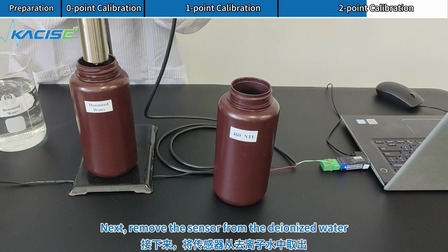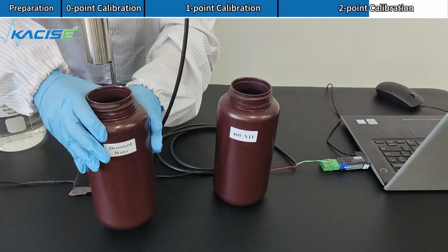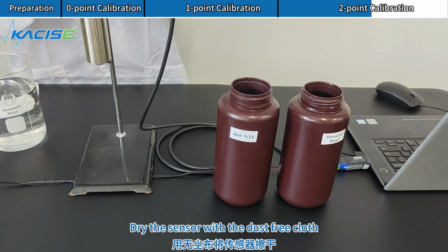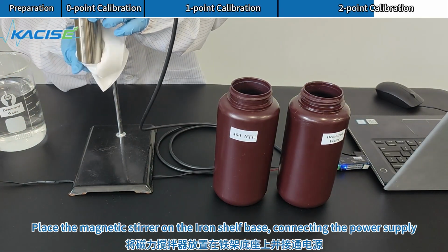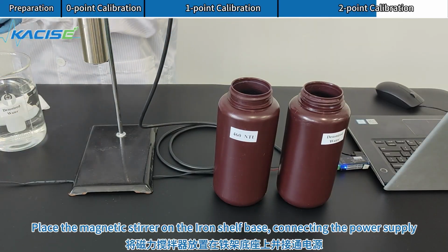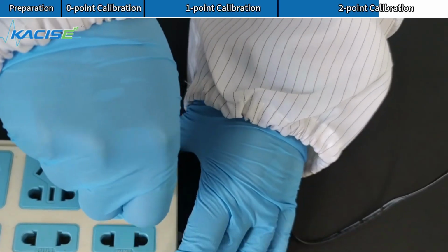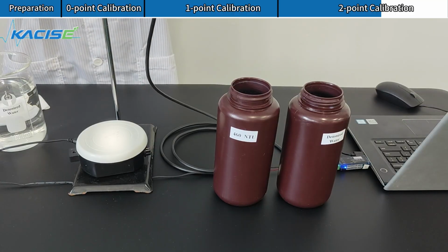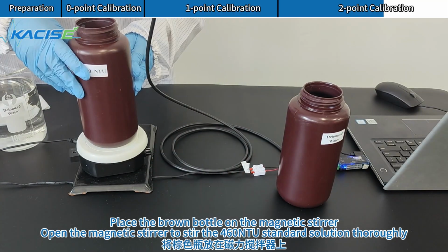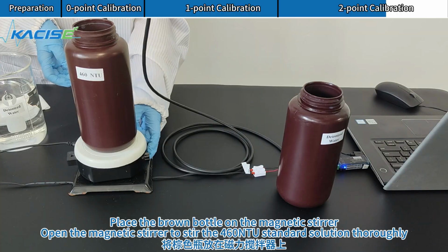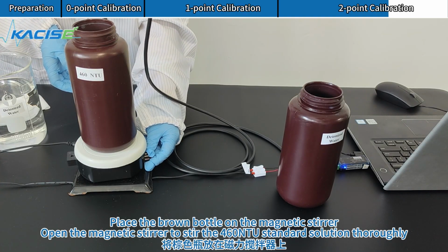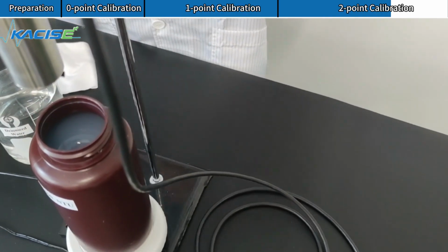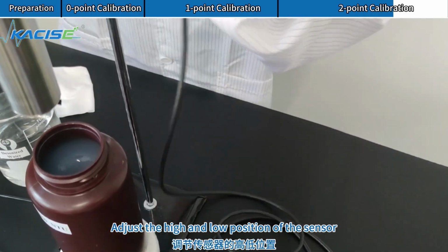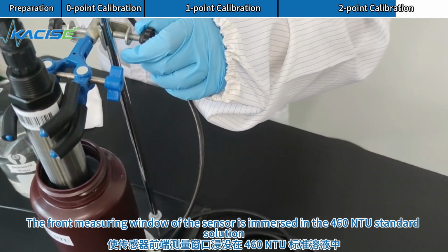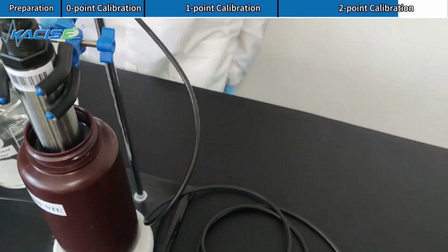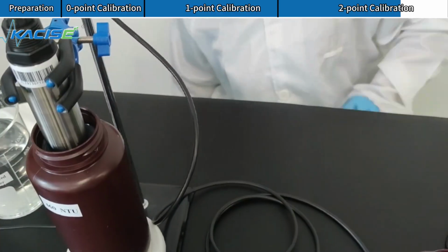Next, remove the sensor from the deionized water. Dry the sensor with the dust-free cloth. Place the magnetic stirrer on the iron shelf base, connecting the power supply. Place the brown bottle on the magnetic stirrer. Open the magnetic stirrer to stir the 460 NTU standard solution thoroughly. Adjust the high and low position of the sensor. The front measuring window of the sensor is immersed in the 460 NTU standard solution.